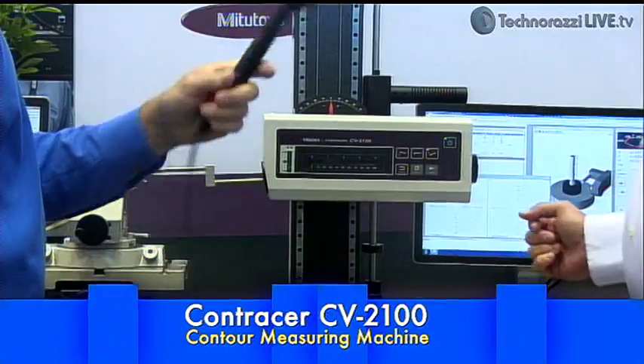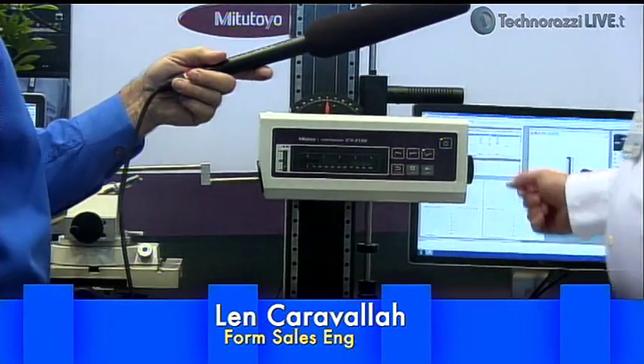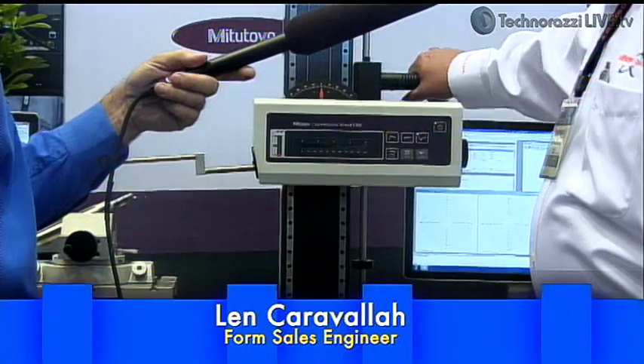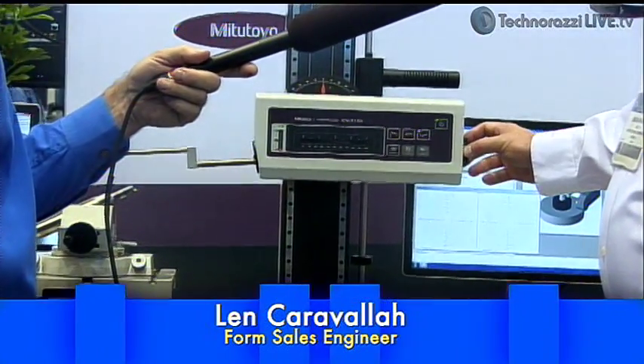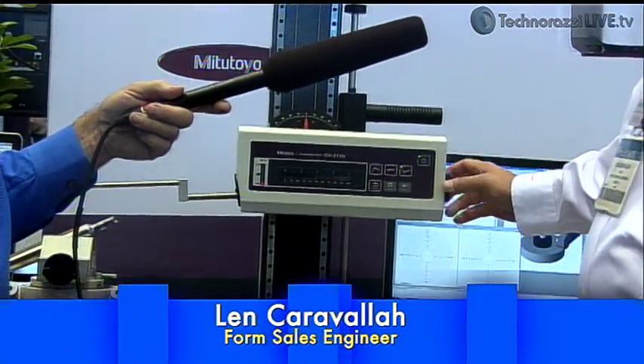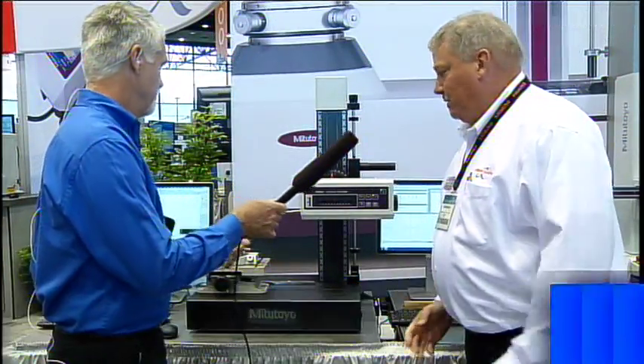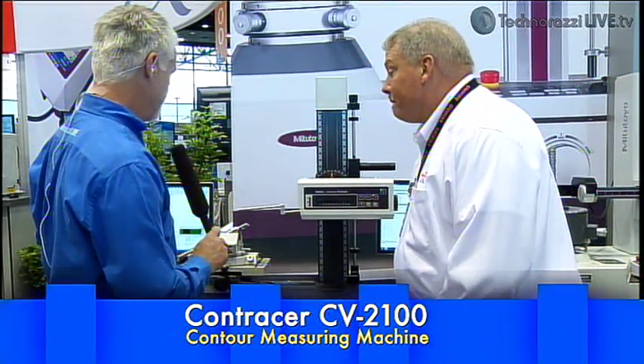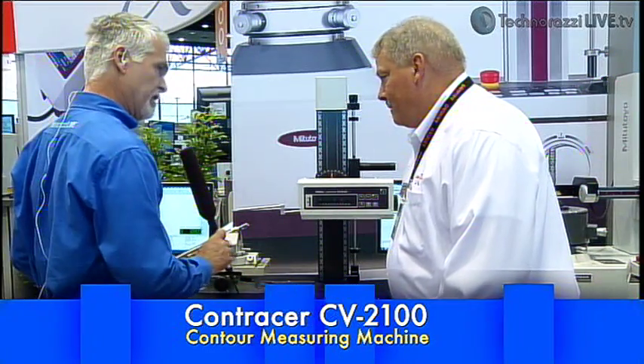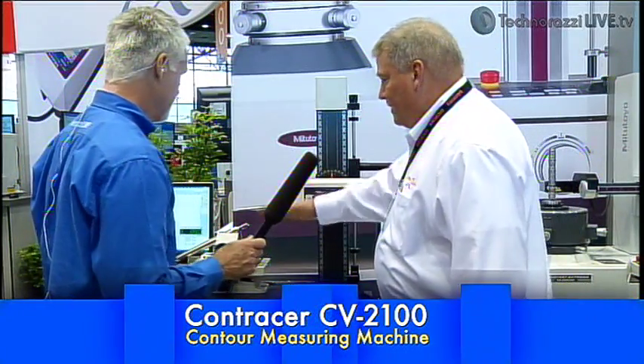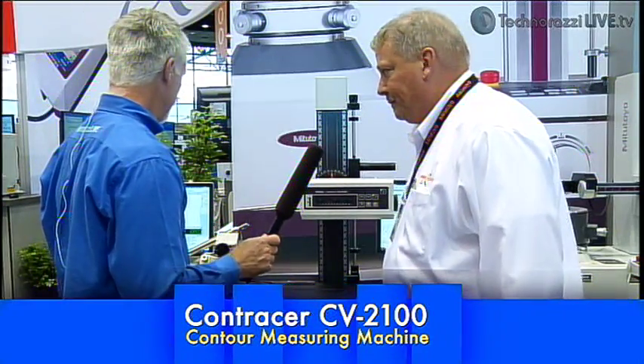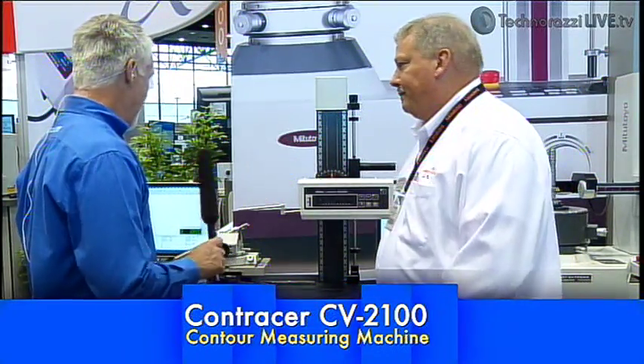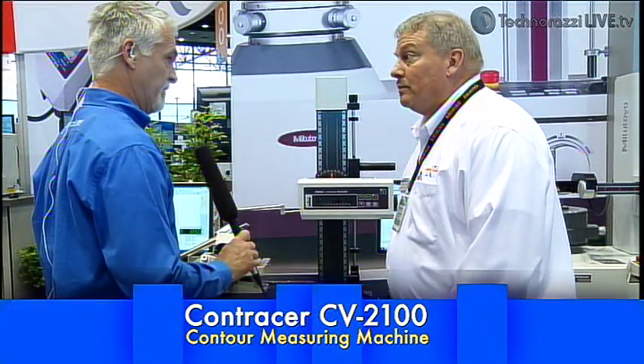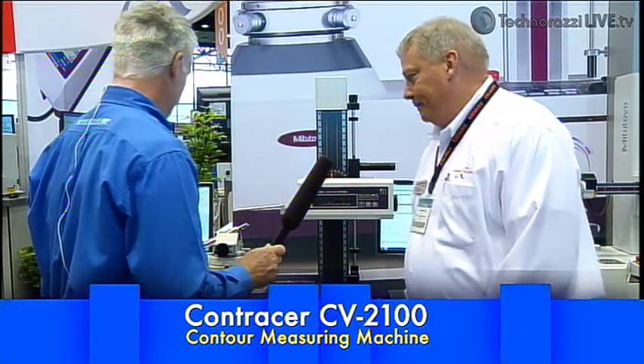Did you say 0.1 micron? 0.1 micron is the resolution, correct. I have a fast positioning in the x-axis by turning this wheel and holding it. Plus or minus 45-degree tilt. And what was the measuring volume of part you could put in this? The measuring volume again is 4 inches, and then I have 50 millimeters in Z travel. Okay. 25 micron stylus tip. And this is form, not necessarily surface roughness. That is correct. It is contour measurement only.